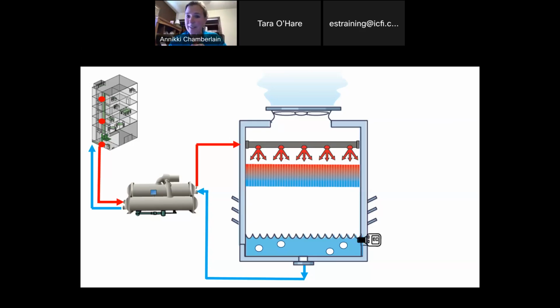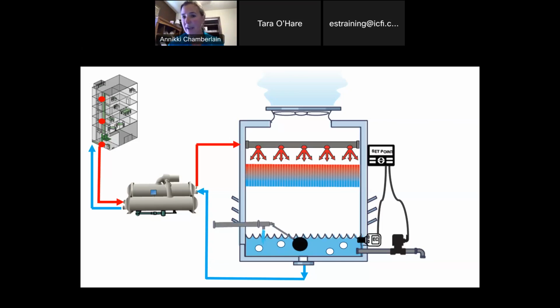So we have a sensor that's monitoring the mineral concentration in the water at all times. Usually it's a conductivity sensor. That sensor is connected to a controller, and that controller has a set point. The set point says, as soon as the water mineral concentration gets so high, we're going to open the drain and drain that tower. Not completely, but we're going to get rid of some of that high concentration water. The industry term is blowdown or bleed, but basically it's just draining the tower. Typically it's a blowdown valve operating that, usually an electrical solenoid valve. So that valve opens up, the tower drains. Well, if we're getting rid of water, what do we have to do? We have to fill the machine back up. So then we have what we call makeup water supply, just a refill.